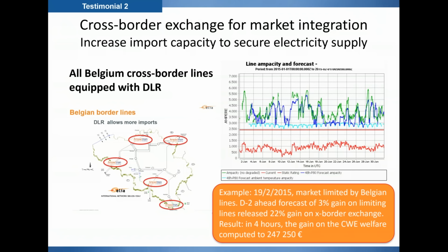And we have now software available. This is commercially available since several years, that tell you, based on sensors and based on weather forecast, what amount of capacity would be available on those interconnectors, for example, in up to 60 hours ahead. So therefore, you can use that on the market. And in this example, we've shown that, and we routinely do that, you can get only 3% of gain on the limiting lines. That would translate to 22% of gain on the whole cross-border exchange. And in that example, in 4 hours, you had saved to the system in excess of 200,000 euros. So again, we're talking about return on investments that are measured in weeks.